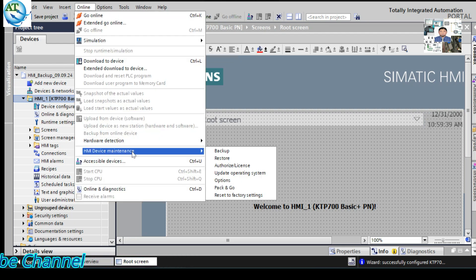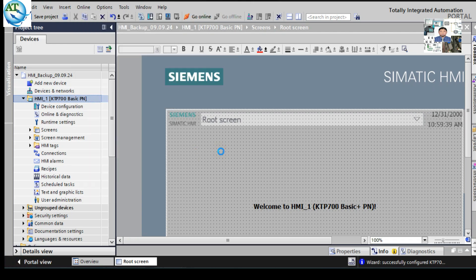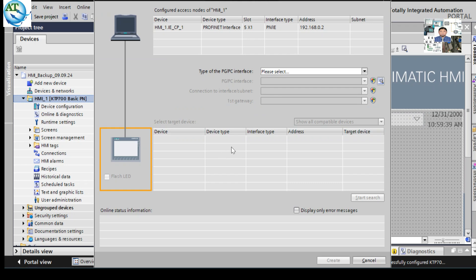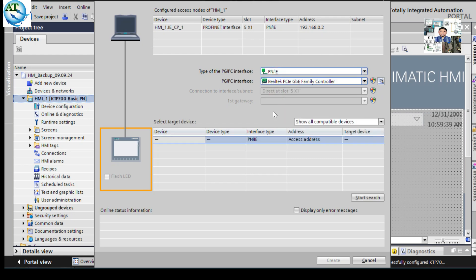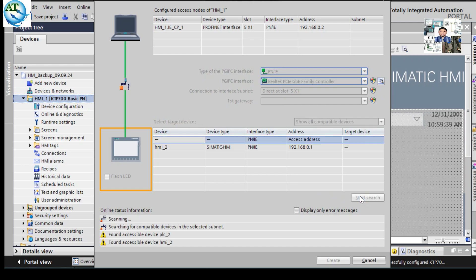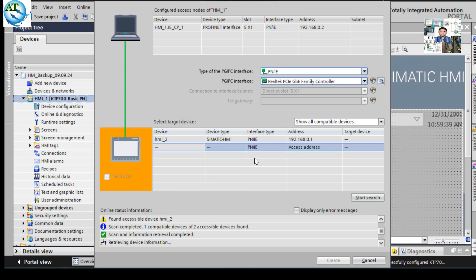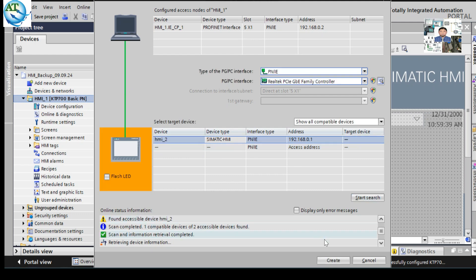Then go to the HMI maintenance. Here there is a 'Backup' option. Since we want to take a backup, press the 'Backup' button. It will go to the communication settings. Check if our communication is OK. Select 'PN/IE' interface — the first PC interface. Then press the 'Start Search' button. The interface will search for the connected device. In the results, find and select the HMI. Then press 'Create' and select to create the connection.